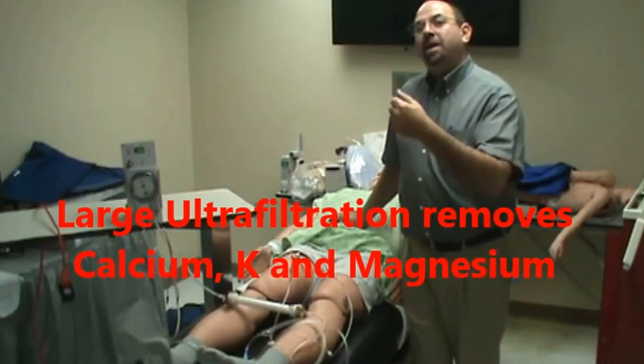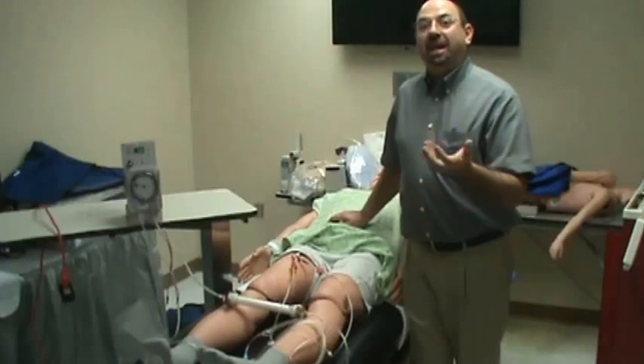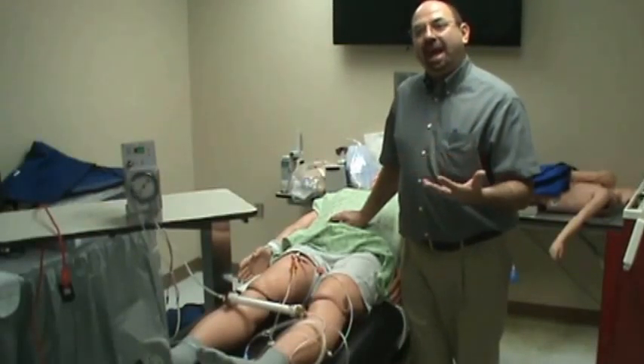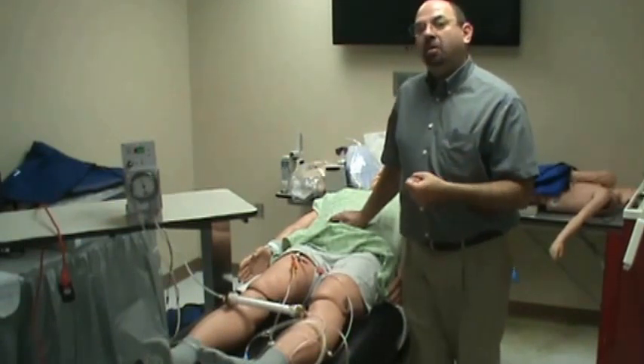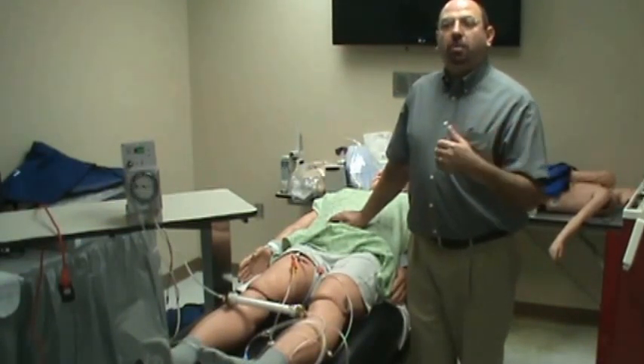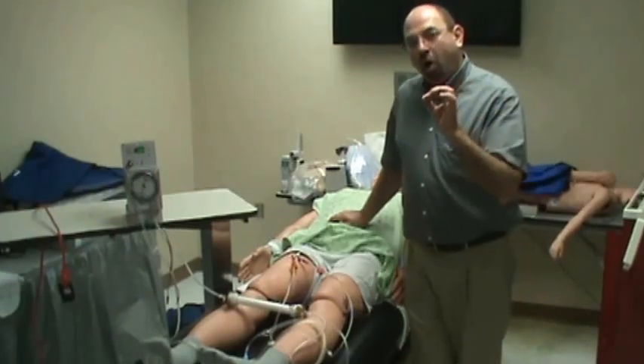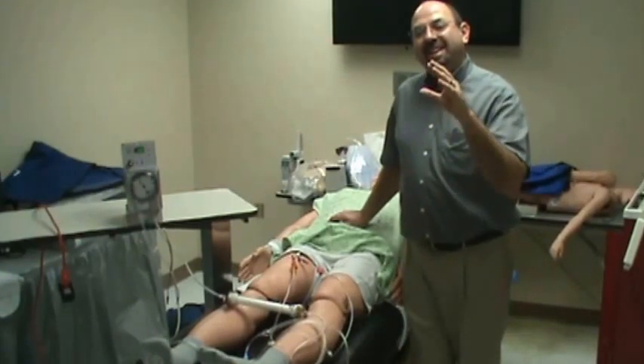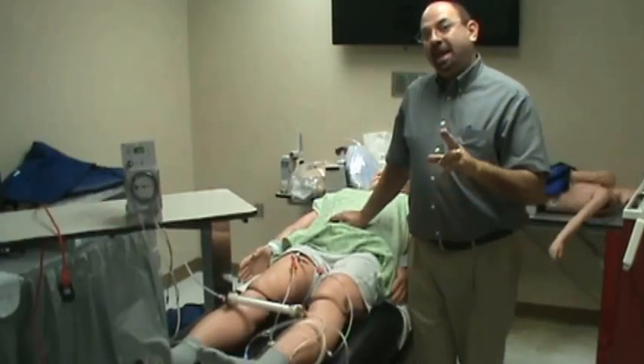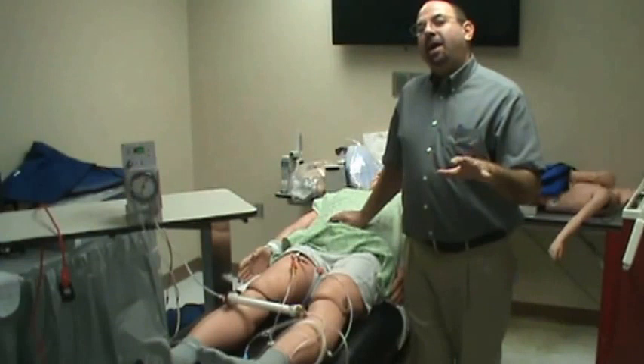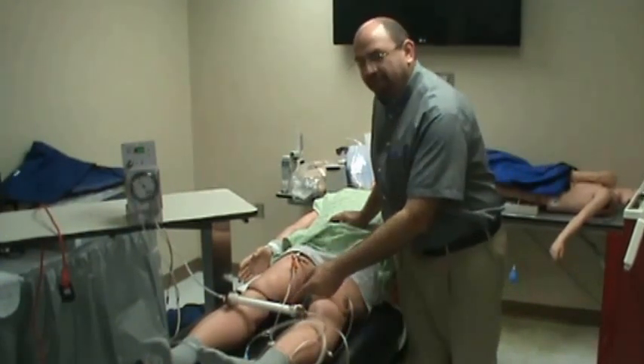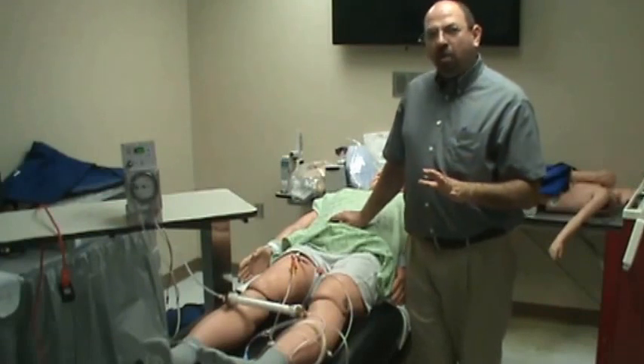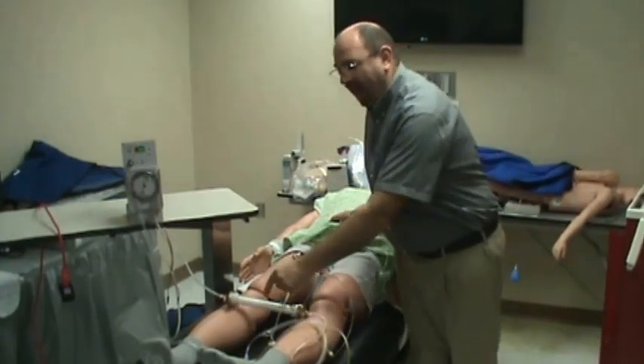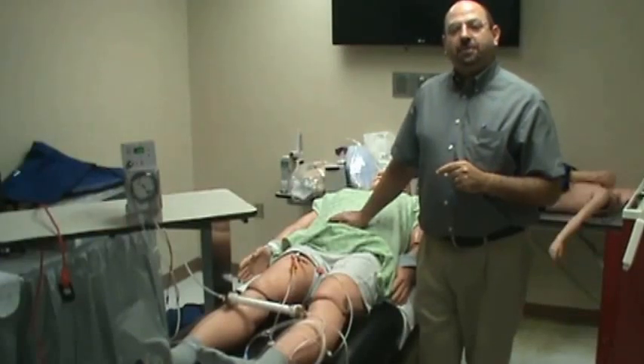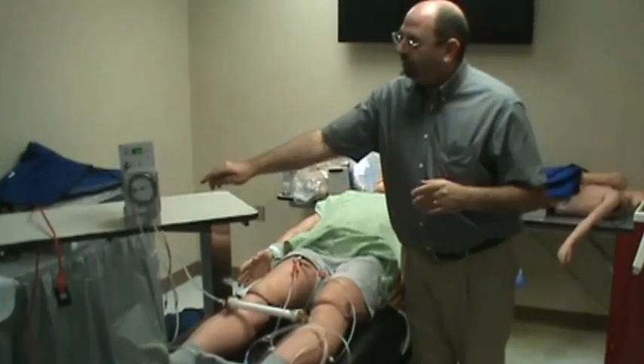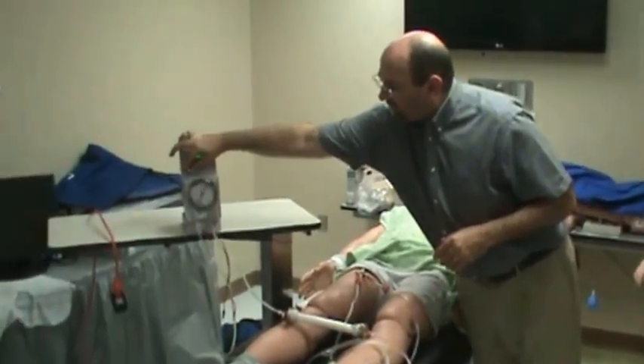So if the calcium is low, you check the calcium every 6 to 8 hours and give calcium as much as needed to maintain an adequate calcium level. If the magnesium is low and if the potassium is low, you replace accordingly. But you always have to have replacement fluid that will contain these elements. Now here's a trick that I will share with you if you want to increase the ultrafiltration. You have to increase the hydrostatic pressure within these fibers. And the way to do that, you can increase the pump speed, and we have this gadget that you can crank up.